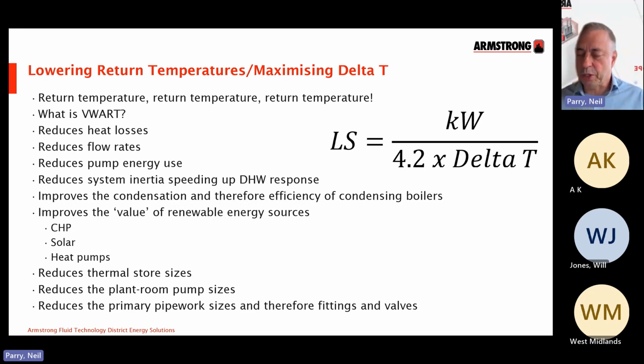But at some point, you're going to come to the point where you've minimized the energy use as much as possible, and you have a figure that is the kilowatts you actually need for that building. Obviously, we can't affect the transfer constant, but what we can do is affect that delta T. And the bigger we make that delta T, the smaller the flow rate that's required to give you that amount of power that you need. So we really need to focus on that delta T. And if we can maximize that, normally by reducing the return temperature, then lots of things cascade down from that.